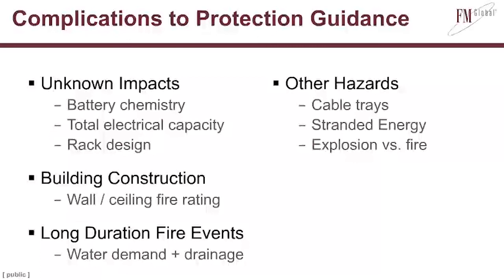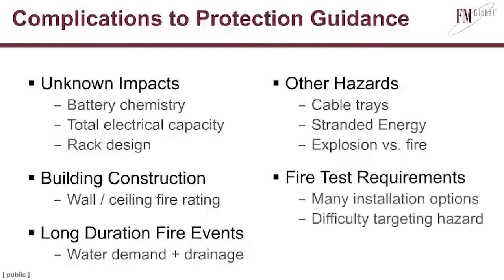You also have stranded energy, and these are made of batteries. So even in the event that a breaker's tripped and the energy storage system is now isolated, you haven't gotten rid of the energy within that battery, and that has implications on fire spread, because as the state of charge of the batteries goes up, so does the reactivity of the battery. It also has an issue of overhaul, because now you could have a lot of energy left over even after a fire. And the last one is this transition between explosion hazards and fire hazards that batteries can do. I want to address that one with my last video in a couple of slides, so we'll get back to that one. The last one I have on this slide is some comment on fire test requirements.